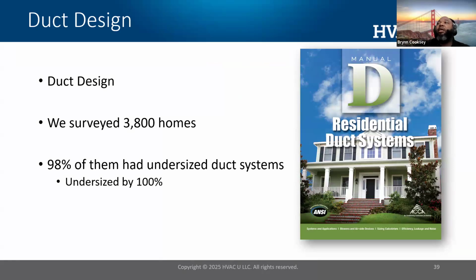Another consideration to look at for heat pumps is the duct system. Is the duct system sized correctly? Like the load calc, we use another design standard called Manual D. Manual D is a residential duct design handbook, and this walks us through all the procedures to do duct design. That same survey of 3,800 homes, we found that 98% of the ducts were undersized by 100%. So not only were load calcs not done for these residences, the ducts were not evaluated either.